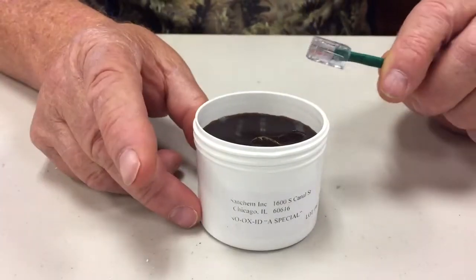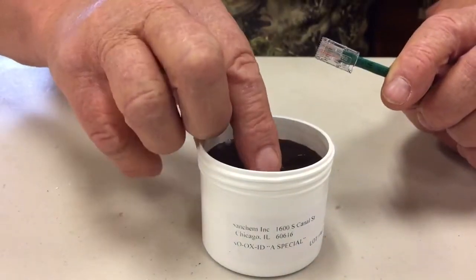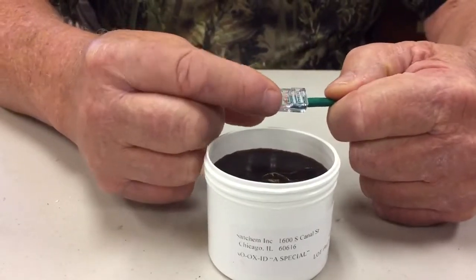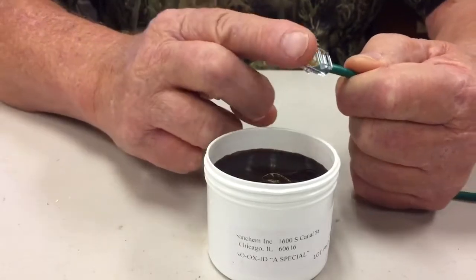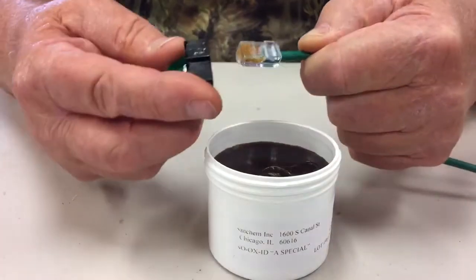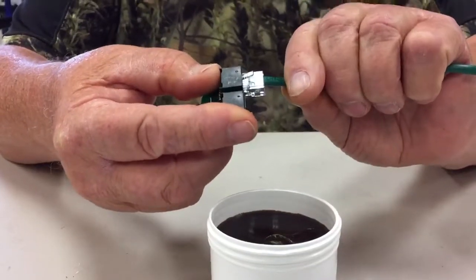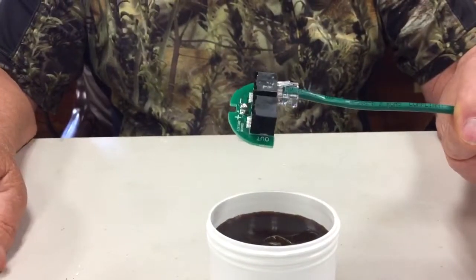Take each RJ45 connector before insertion and place a small amount of NO-OX-ID on the tip of your finger and wipe it onto the connector. Then insert the connector into its corresponding jack. This will protect the connection from corrosion and make the system far more reliable.